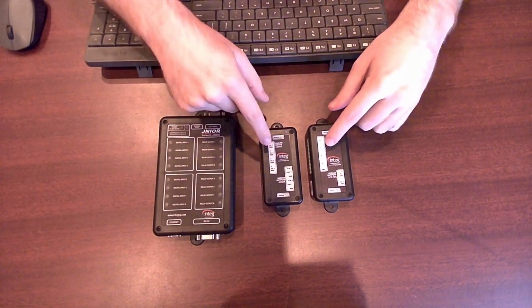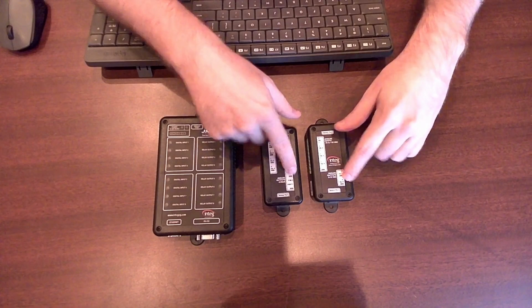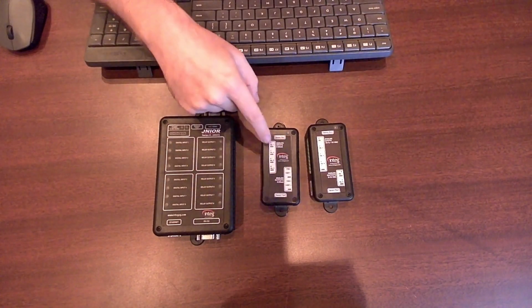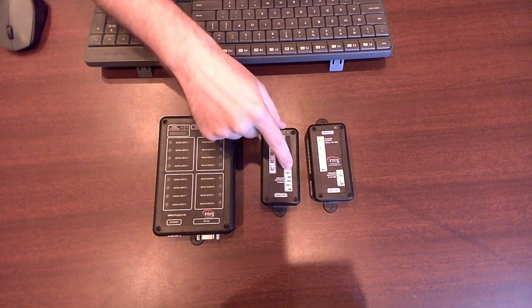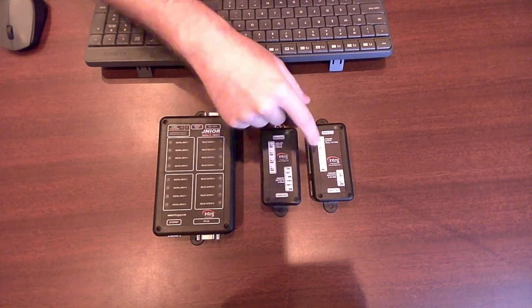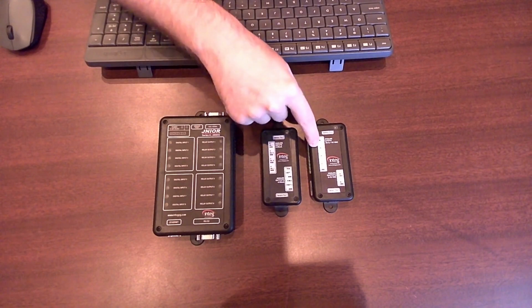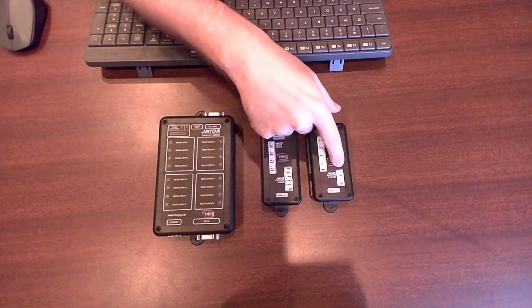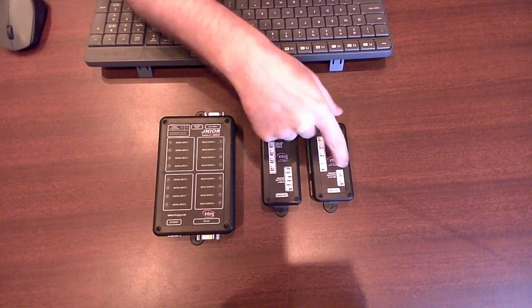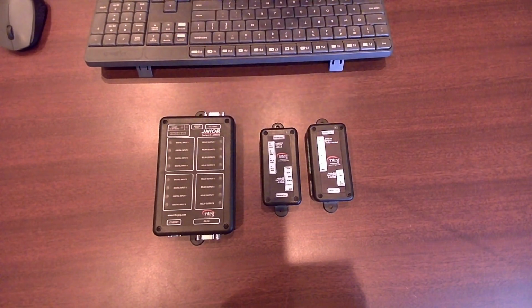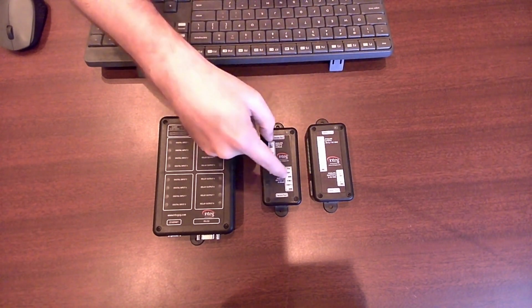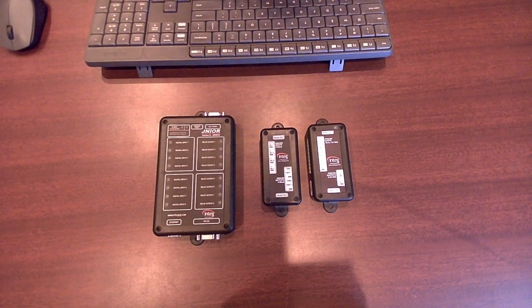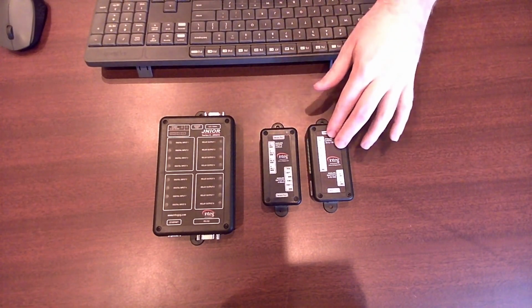Both expansion modules have 4 inputs and 2 outputs. For the 4-20 mA module, it can receive 4 to 20 milliamps on its inputs, and it can give out 4 to 20 milliamps on its outputs. For the 10-volt, it can receive negative 10 to 10 volts on its inputs and can give out 10 volts on its outputs. For the 4-20 mA module, in order to supply power out of the outputs, it requires an external power supply, but the 10-volt does not.